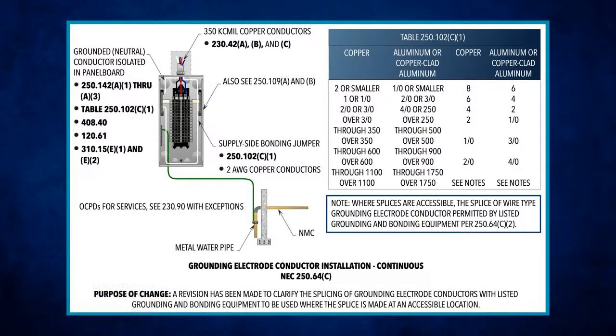Well, another thing that gets interesting, and I like to pull these little things out that make them think, is when you start looking at these different sizes. They have certain requirements in there, just like we're looking at 250.64(C), where it talks about continuous when you're dealing with the type of electrodes and where they're going to. And we've run this before as a myth. I might actually have to do this again, because what is crazy is that you taught me this, King James. It's electrically continuous. It's not physically continuous.